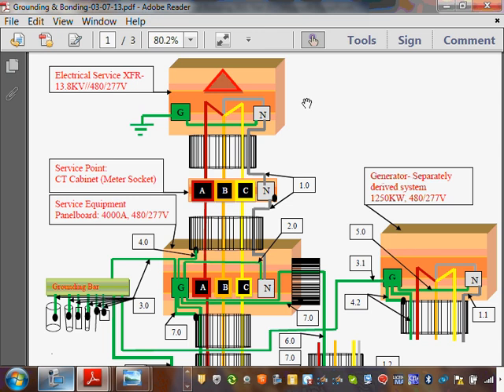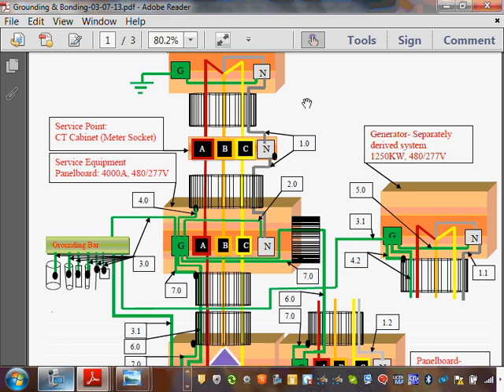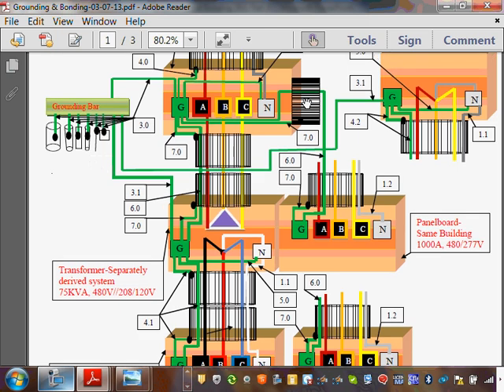So, okay, now that we grounded the system, we brought the neutral, we grounded the neutral, we created the grounding electrode system. I'm going to take 3 very important, different feeders out of this switch gear and ground them and bond them, right? Why? You're going to see why I picked these feeders, because these are the most common and their grounding and bonding is slightly different. The easiest one, guys, is the first one. So imagine taking a 1000 amp feeder from the 4000 amp feeder into another switch board or switch gear. Don't let the amps scare you. That could be, like I said, 60 amps from a 225 amp panel or 200 amp panel in your house. Really the same thing. The only difference about this panel is it's the same building. There's a big thing when it's in the same building. The grounding and bonding is different if it's a separate building.